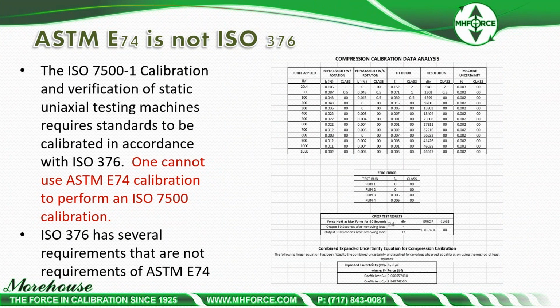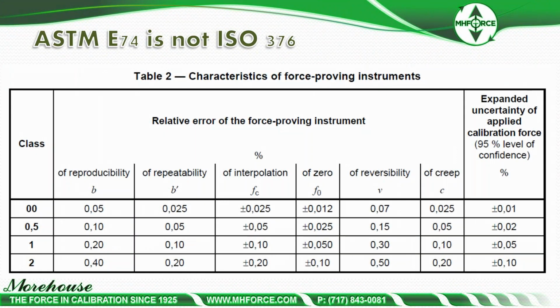ASTM E74 is not ISO 376. We have a whole class on ISO 376, a whole presentation, but ISO 7500-1, calibration and verification of static uniaxial testing machines, required standards to be calibrated in accordance with ISO 376. You simply cannot use the ASTM E74 calibration to perform an ISO 7500 calibration. ISO 376 has several requirements that are not requirements of ASTM E74. Some of these requirements are as such. Well, let's look at this.